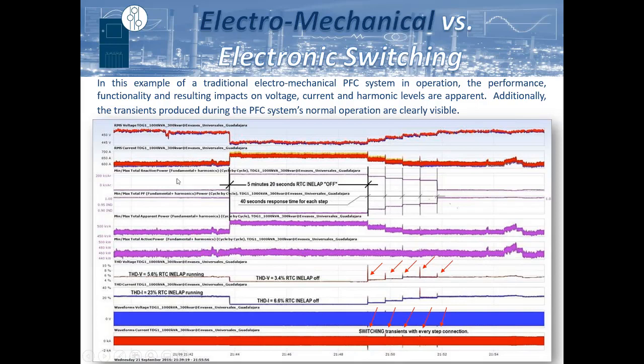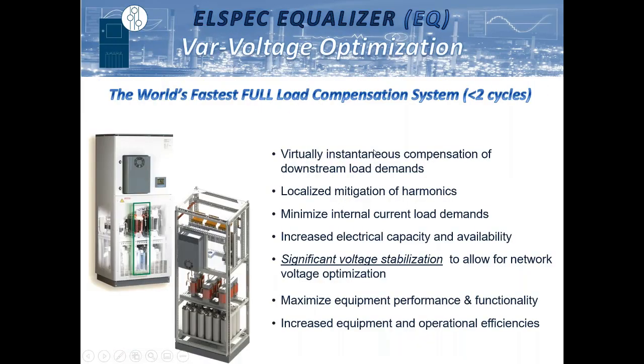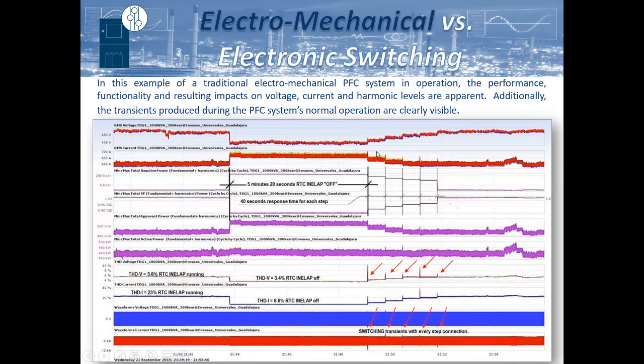And in order to ensure that it doesn't go over capacitive, they generally operate with a corrective response every 20 to 30 seconds. You can see here some measurements that were taken on a network that had a traditional power factor correction system. We disengaged the system for a little over 5 minutes and then re-engaged it, and you can see the impact. Without the system engaged, it had a very low voltage level on a 480 volt nominal or a 460 volt nominal. Then as it brings in each group, you can see the voltage level rise. But any of the moments in between, it can't respond, so it can take over 2.5 minutes to actually get a full load demand response.